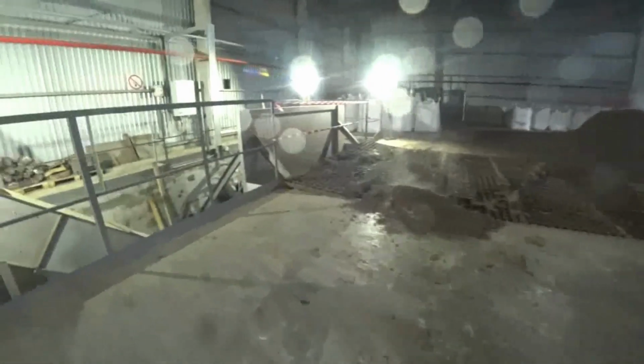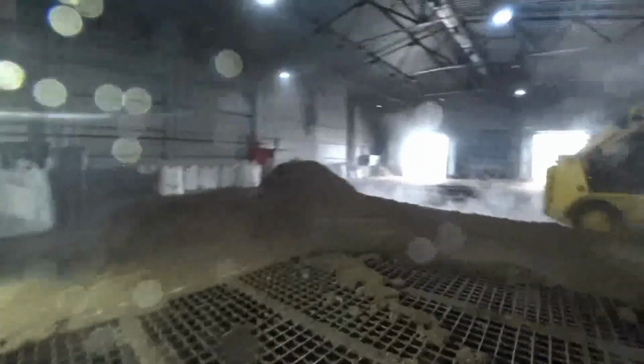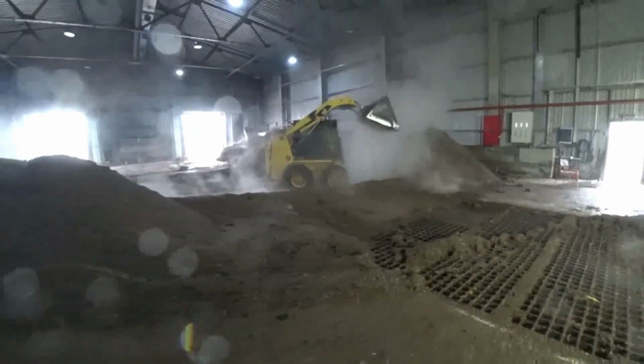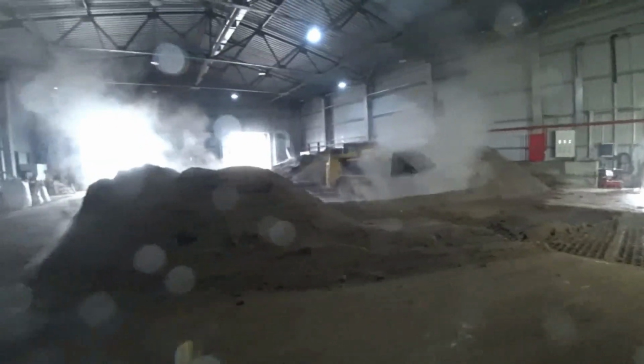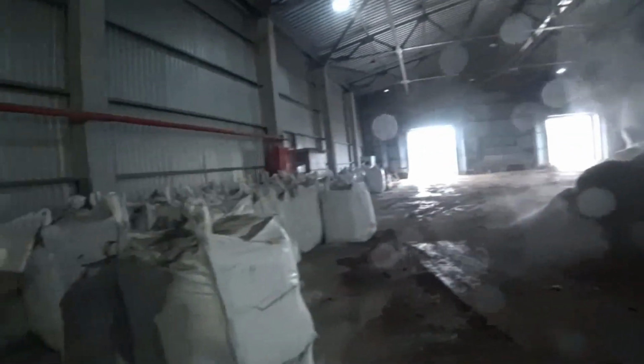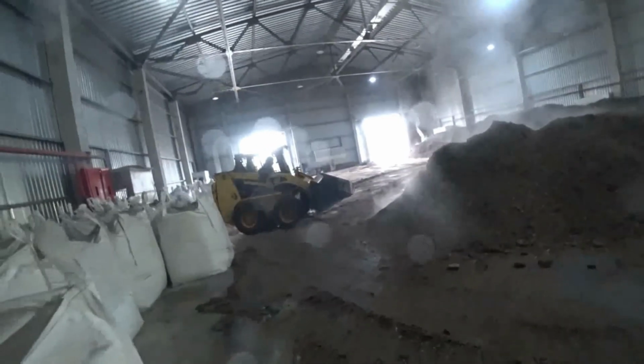In front of us is an operational mechanized bunker, live bottom. The bunker's volume is sufficient for 3 hours of operation of the complex. Directly under the roof are the air ducts of the exhaust system. The warehouse also has the ability to temporarily store ash after burning biofuel. The main fuel is manure. From 5 to 15% of sunflower husks are mixed with manure. The poultry farm uses the husks as bedding when growing poultry.